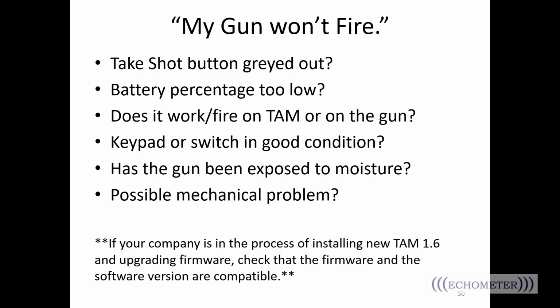So, like most equipment, if it's running on battery power, when you fire the shot, once you click that acquire button and you see that fire button flashing, you've got that capacitor in there, and it's trying to build up enough energy to fire the shot. Well, if the battery percentage is too low, it may not have the capability to do that, right? So we recommend that if your battery percentage gets to around 30%, go ahead and find a power source and recharge that battery.